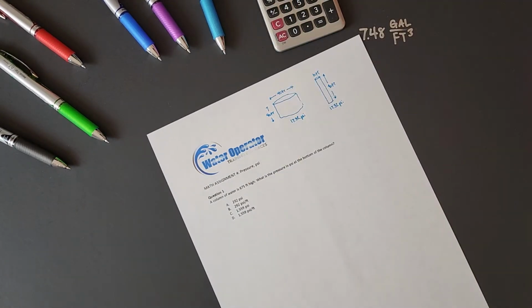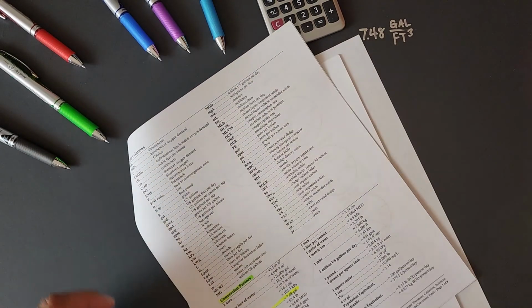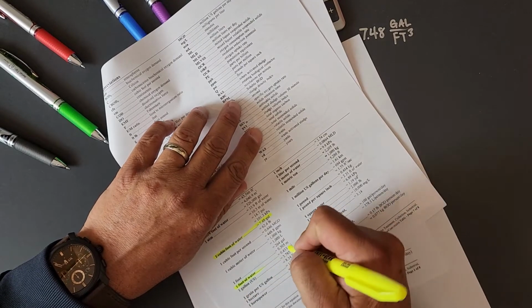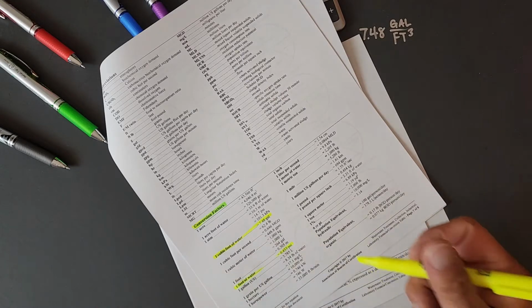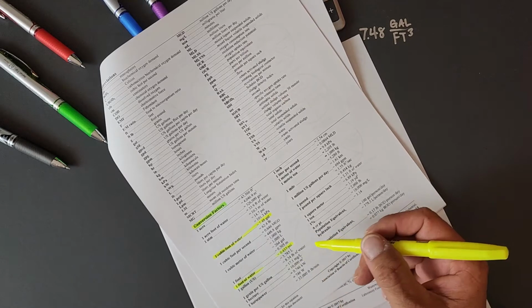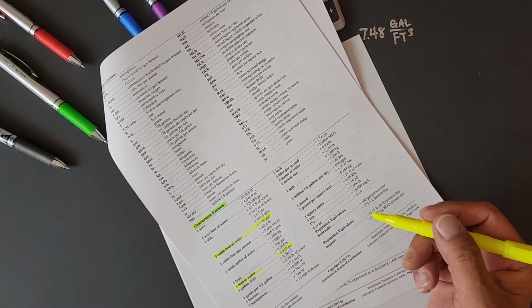Okay, now that we have that straight, let's figure out how to make these calculations. If we go to our ABC math formula sheet, we can see that 1 foot of water is equal to 0.433 psi, just under half. So if I have 10 feet of water, I know that the pressure is going to be less than 5 psi. In fact, it's going to be 4.33 psi.